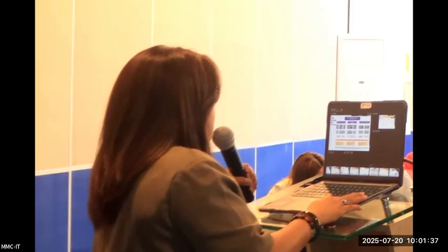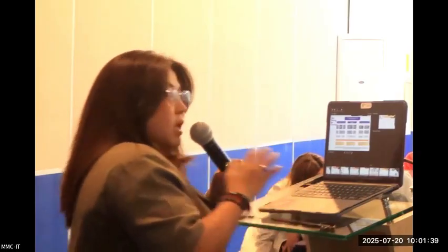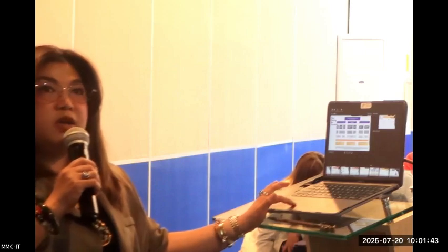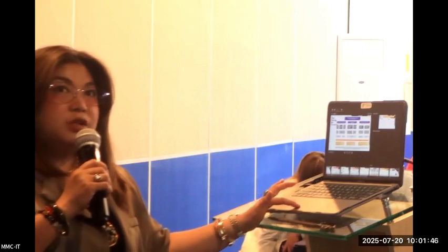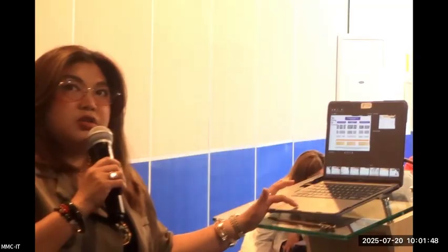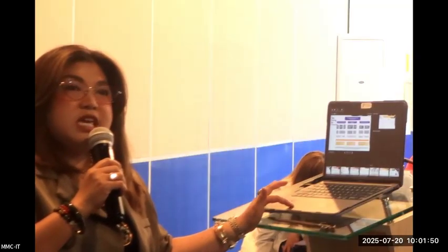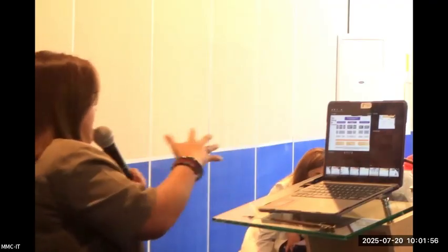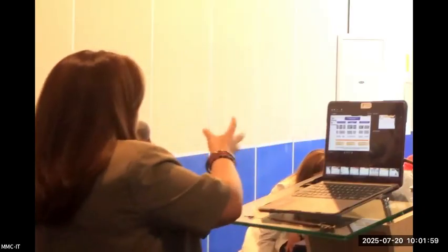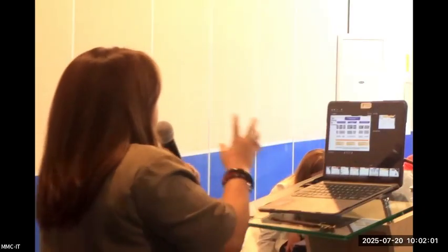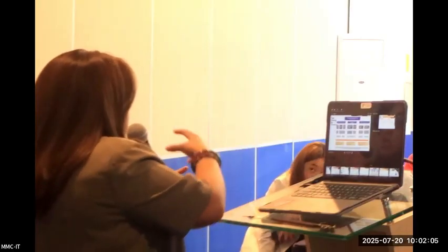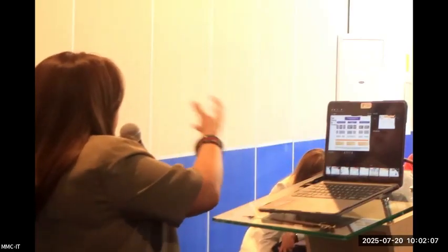Okay. So this actually shows you what type of procedure you will be performing. For example, your external, your interventional, and your internal transducer procedures. As you can see here, depending on the level of use of the probe, you have to clean your probe depending on whether you use a cover for your probe or not. But prior to that, it's very important to disinfect it and then place a cover or the one provided by the company of our probe.